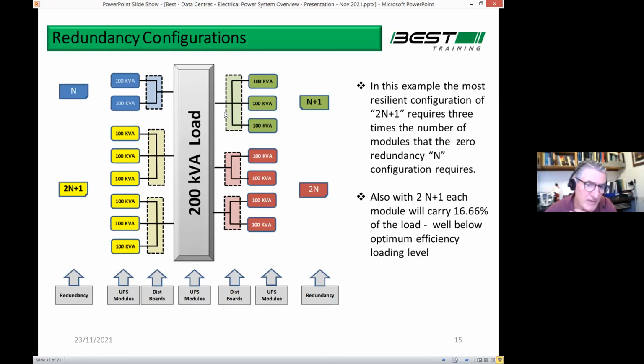The problem with that arrangement is you still only have a single power path into the load. So if the switchgear associated with this UPS system failed, or the main cable, or the busbar system in this board failed, you would lose the entire UPS system. So that's why the next one is probably the most popular thing with critical loads, and UPS systems are often done in a 2N configuration, which means you have an A system and a B system, and both systems are capable of meeting your needs.